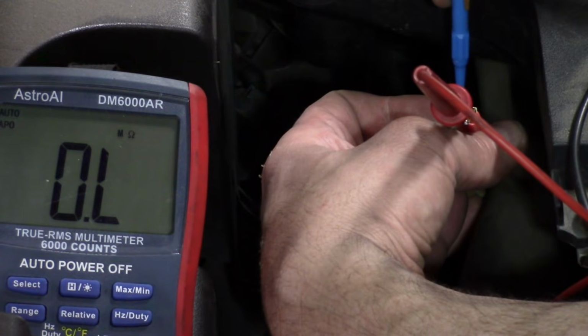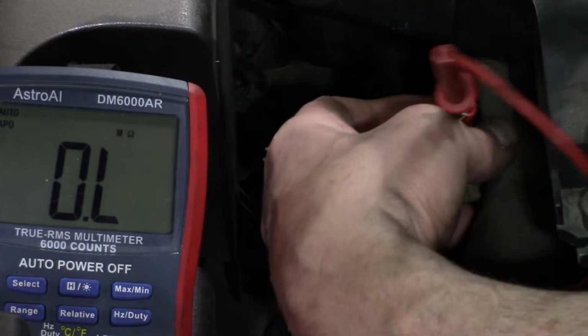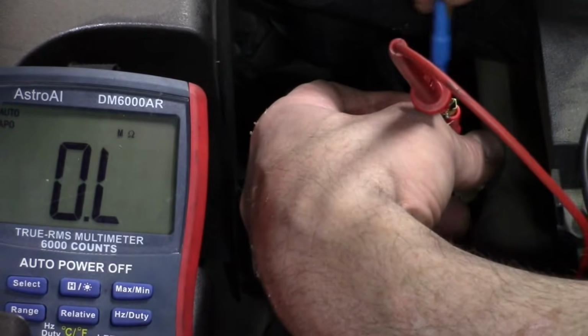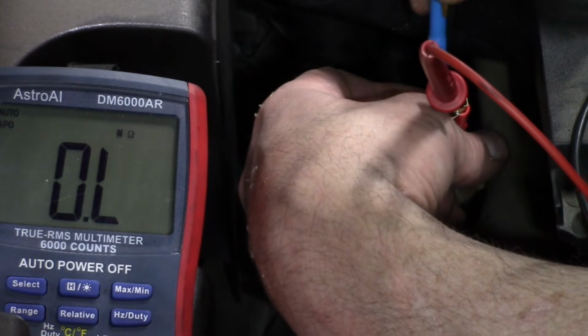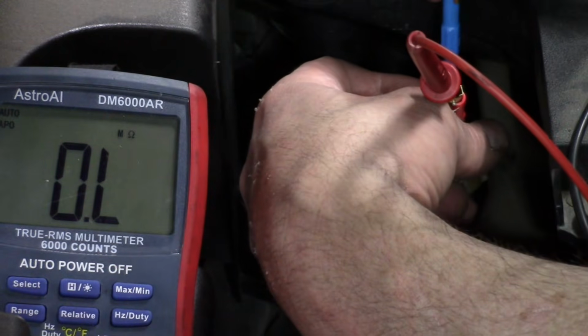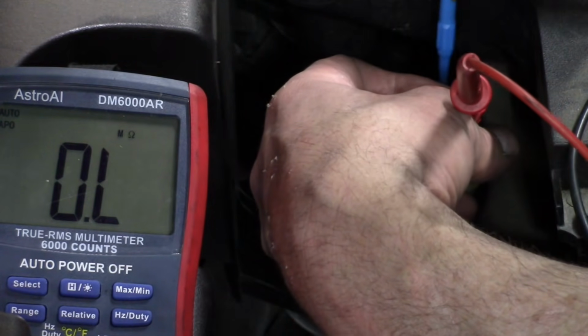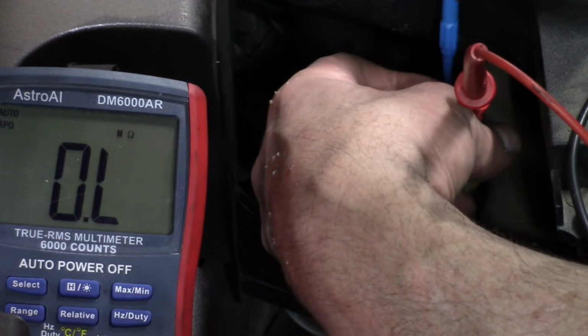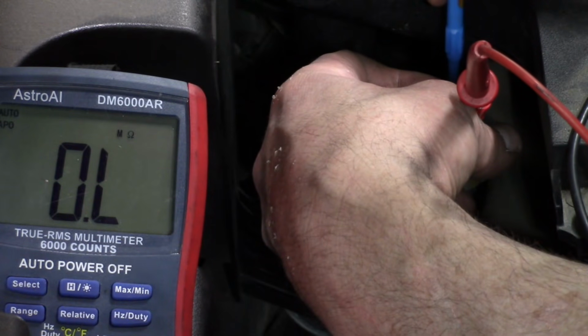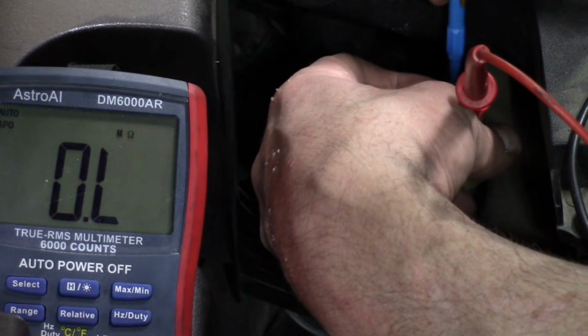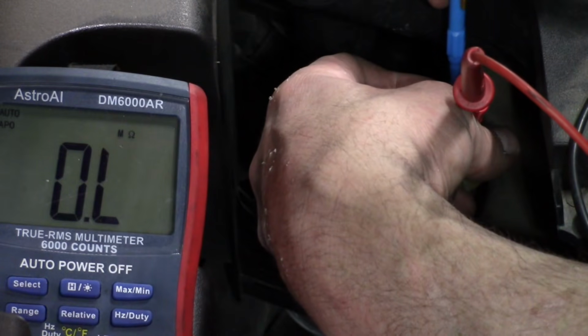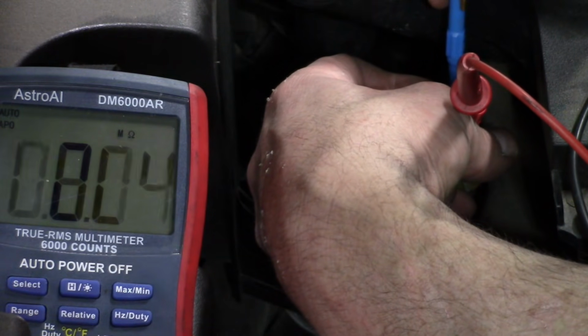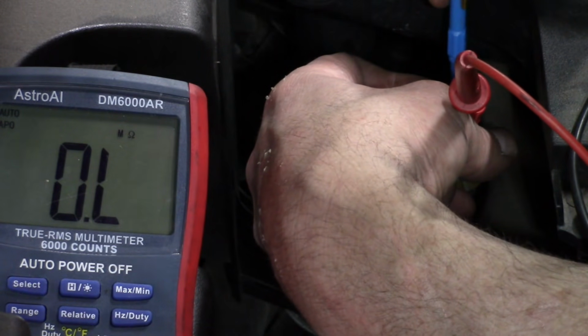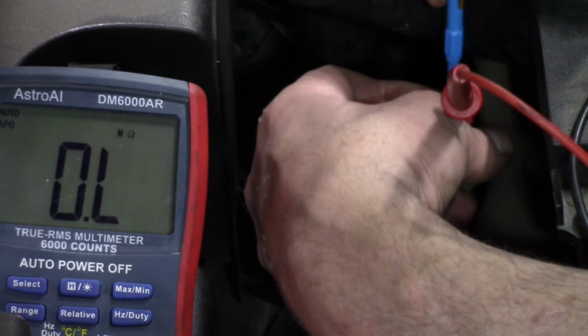It's still reading out of limit. It's not unusual that you may sometimes see a reading here, but if you tap on the sensor, you lose it. That's because when these heater circuits fail, sometimes that filament, like a light bulb filament inside the sensor, still makes contact even though it's broken just a little bit. So you might see a little bit of reading sometimes. Right now we're seeing just out of limit.